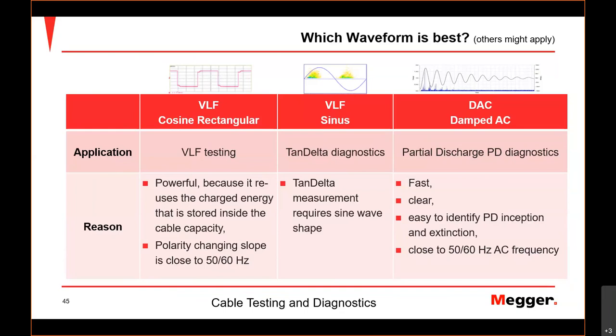People are complaining and say, oh, we cannot do the whole test for 1 hour, but you should. This was one of the main points in the previous webinar, because in plastic cables you have a process. These water trees that I mentioned are a very slow growing process, and by slow I mean 5 to 15 years. When they are big and become critical, we can convert them into electrical trees. That's a little bit of arcing, which is actually partial discharge, and we can see that with partial discharge.